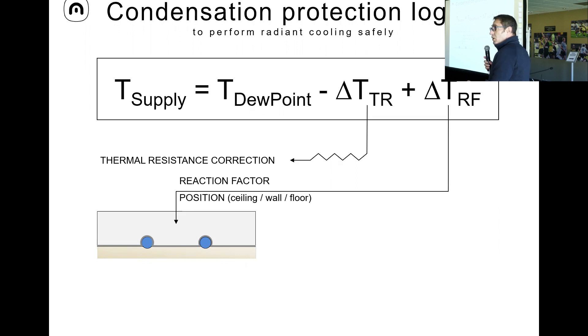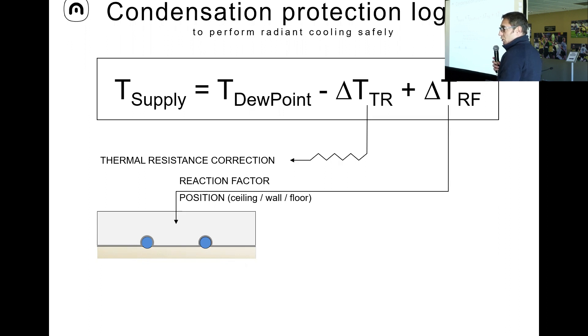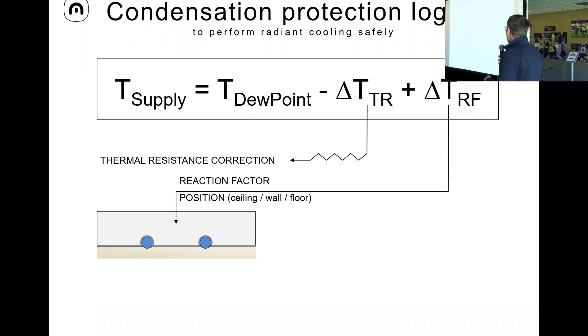The safety factor is based on thermal mass. On the floor, you could drive the temperature very close to the dew point, but if you need to brake it would take too much time — the reaction factor of the floor is much higher. That's why the floor is not a good candidate for effective radiant cooling. There are also comfort reasons: you don't want the floor too cold, as it may be uncomfortable, especially if sitting for a long time. Radiant cooling on the ceiling is much more effective.